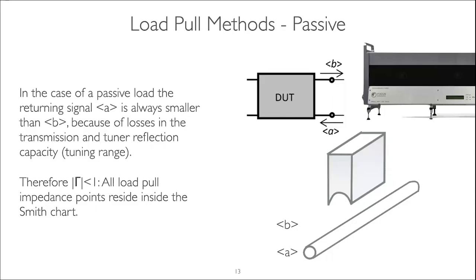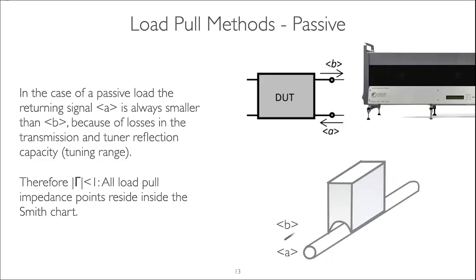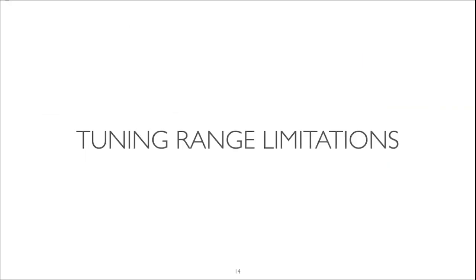But as we bring the probe down and you inject the same B wave, well now, depending on what position you are in, you're reflecting that wave back, and now you'll have a component in the A wave, and that's how you basically create the impedances and control them over the Smith chart. Okay, so we'll talk about how we do this within the tuners here. So the big thing with passive tuners is the tuning range limitation. A passive tuner will not be able to go outside the Smith chart like an active system. So at the tuner reference plane, you're limited within the Smith chart. Now, as you add loss, such as a cable, adapter, or probe, this will limit the tuning range, okay?